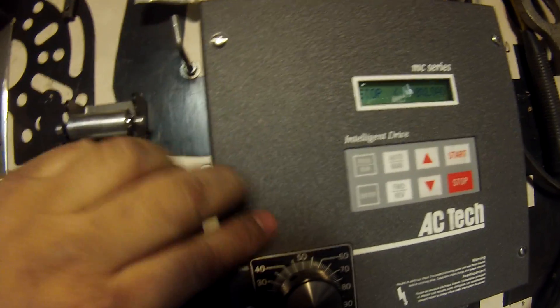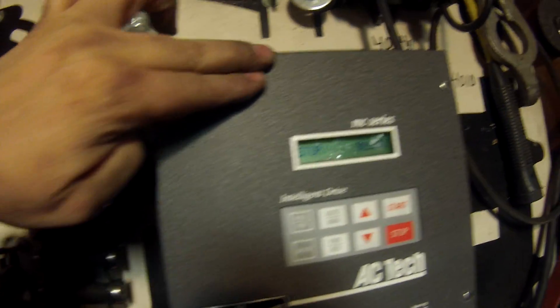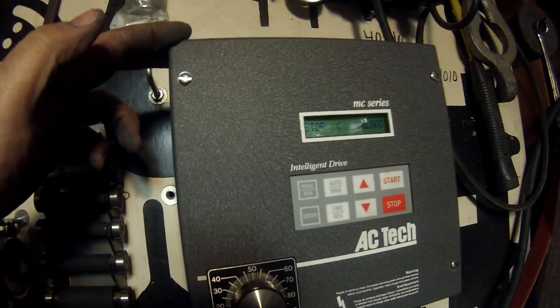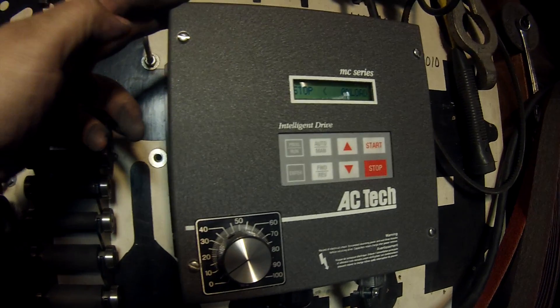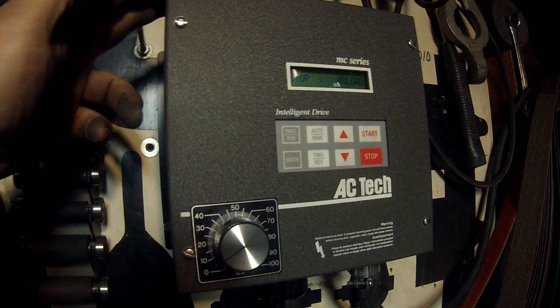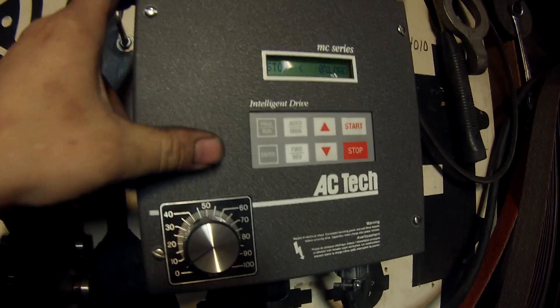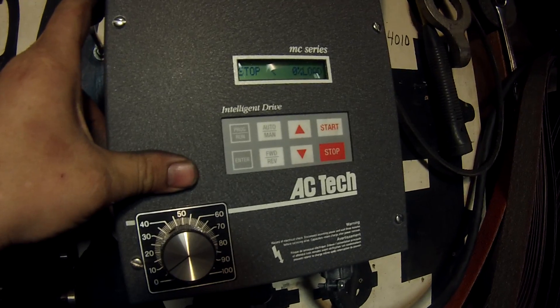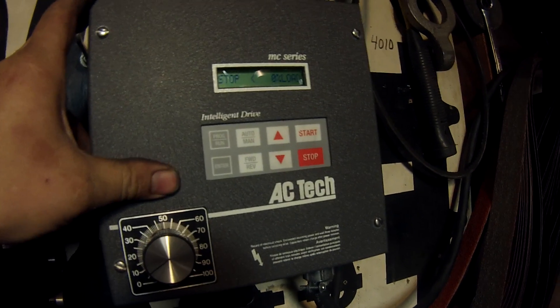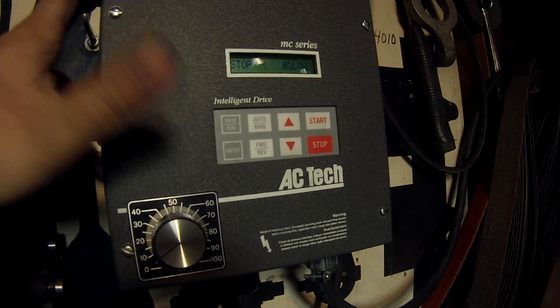Inside of here it has six capacitors. It's got a whole row of capacitors here and then across the top. You really need that when you stop and start such heavy wheels. If you don't have enough power or a good DC injection braking system in the drive, which a lot of drives don't have any type of braking, it will trip it.